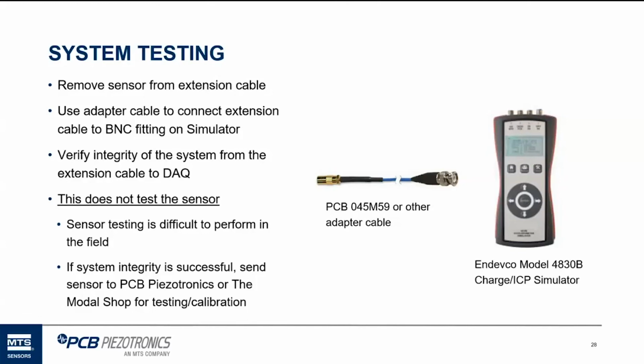So if the customer doesn't have a spare sensor, the best thing they could do would be to send it to PCB or The Modal Shop to get it tested, calibrated. There are some sensor testing devices for field, but they're really inconvenient. They're not easy to use. They don't provide a great test. So, you know, I think this is a real, I'm going to say, cheap and easy way to test the system and find out if the sensor's good or not. But, you know, our sensors don't typically fail.